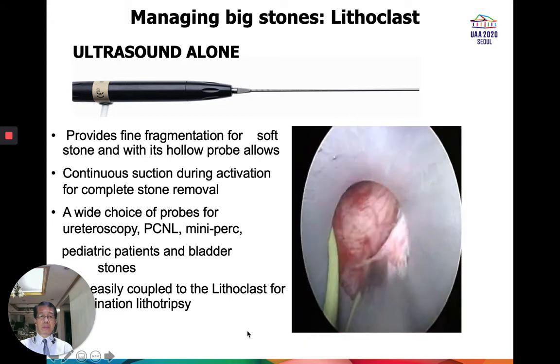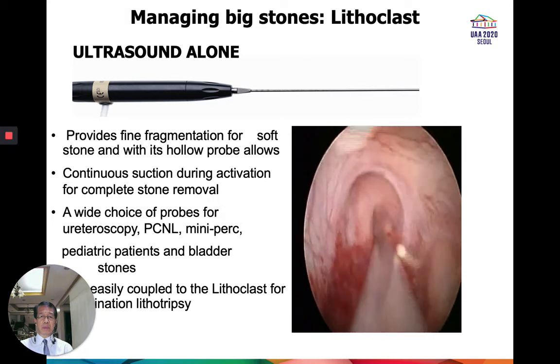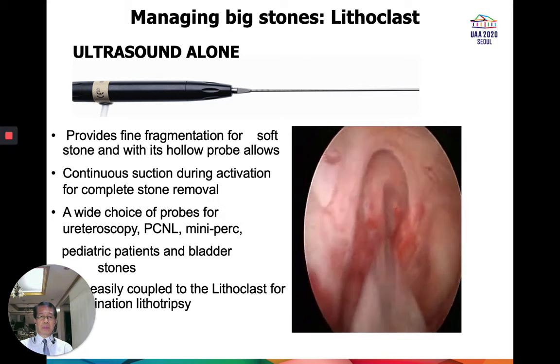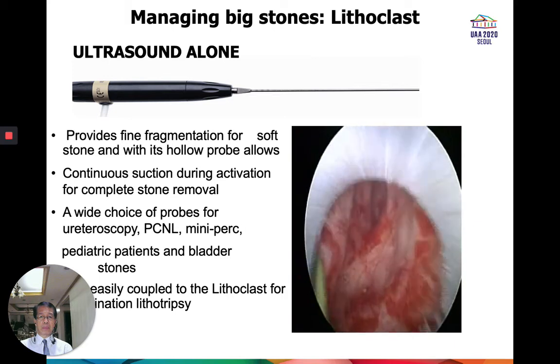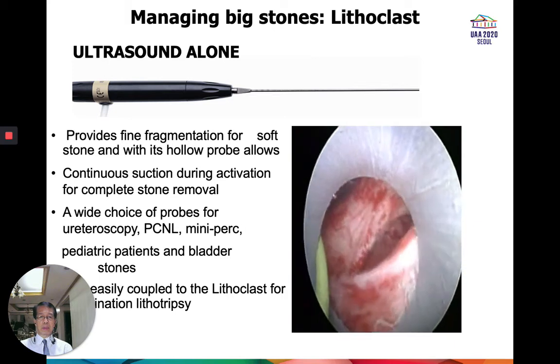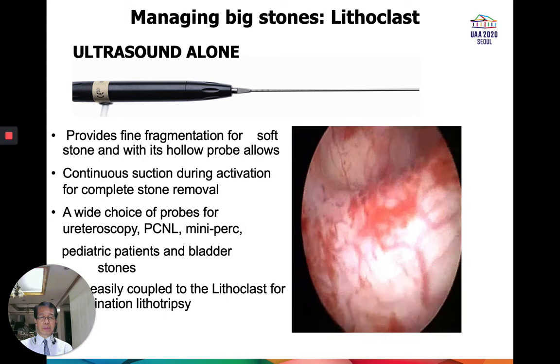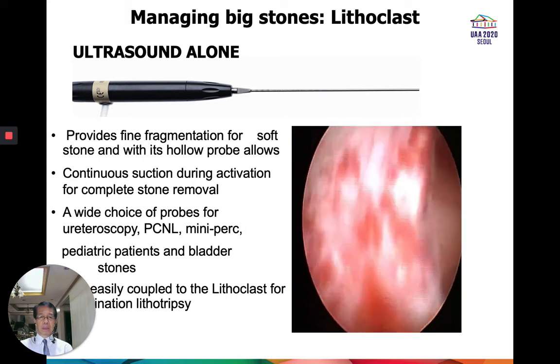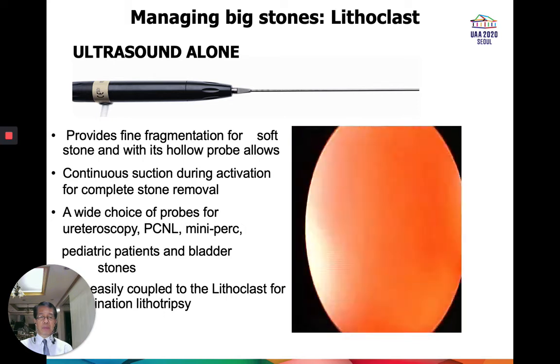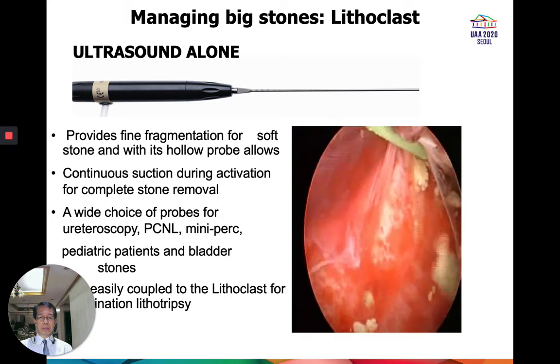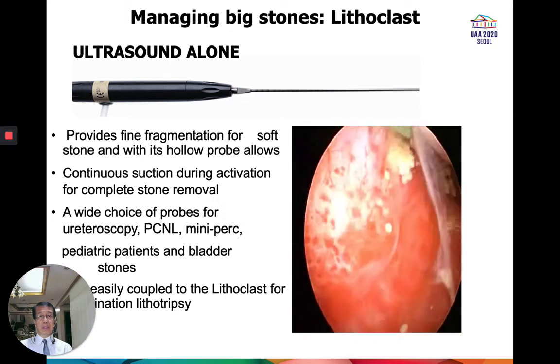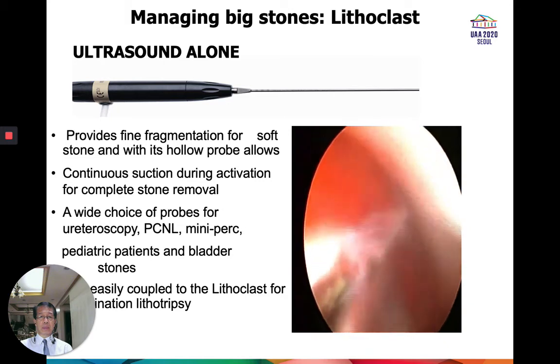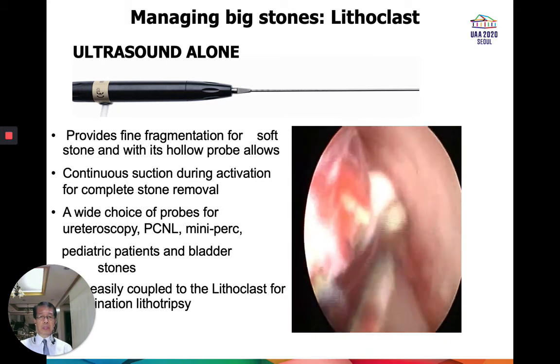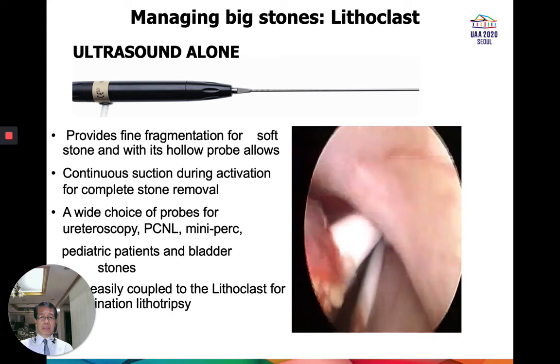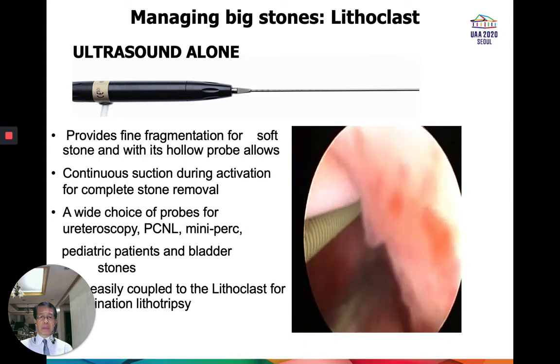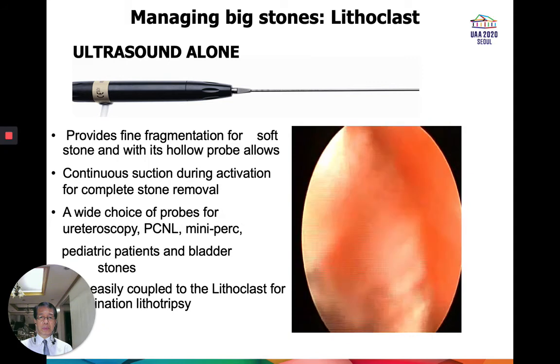The ultrasonic system provides fine fragmentation of soft stones, and with its hollow probe, one can continuously apply suction to completely remove the smaller fragments. The probe comes in different sizes and therefore can be used in ureteroscopy, standard and mini PCNL, in pediatric stone cases, as well as for management of bladder calculi. It easily couples with the pneumatic Lithoclast for combination lithotripsy.